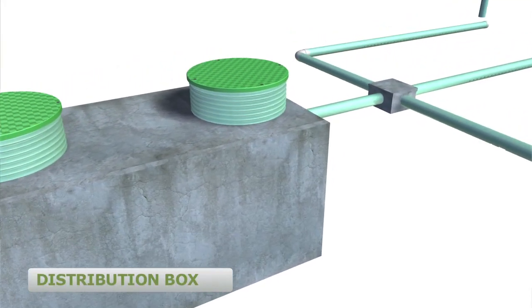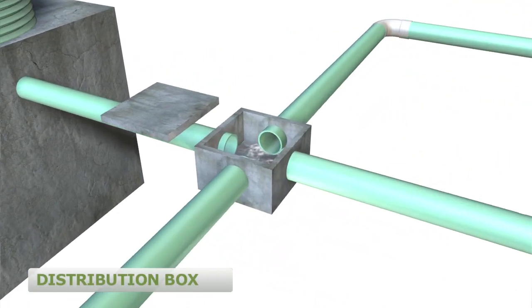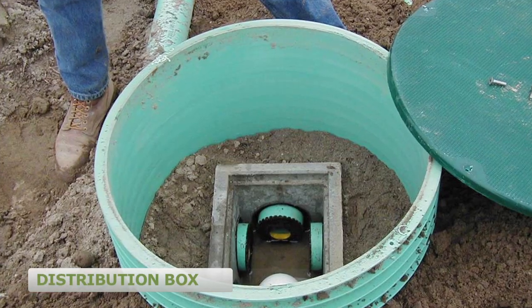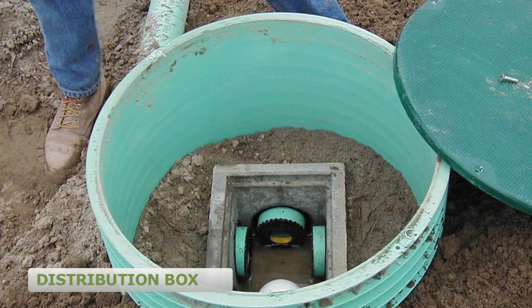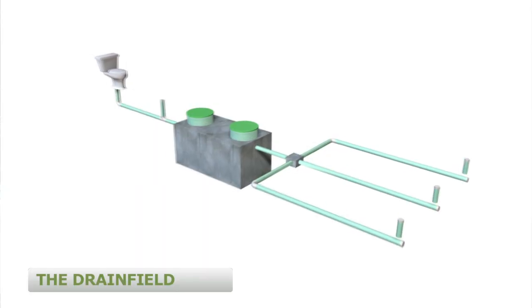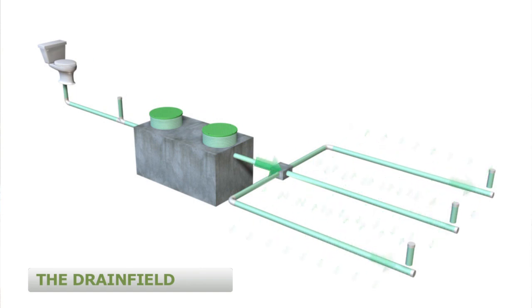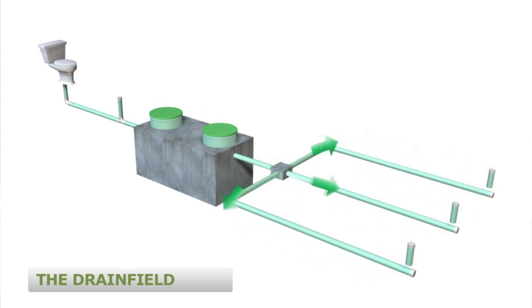Typically, gravity systems will utilize a distribution box, or D-box, to equally distribute the effluent into each lateral pipe in the drain field. Equal distribution of the wastewater into each lateral is critical to the long-term operation of the drain field. Once the effluent reaches the laterals, it flows out of small holes and into the surrounding soil, where aerobic or oxygen-loving bacteria and other microbes treat the wastewater by removing pathogens.